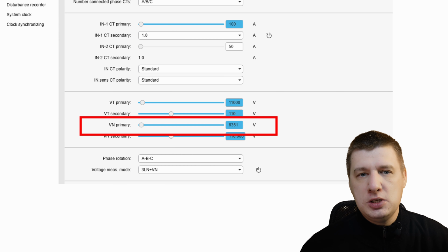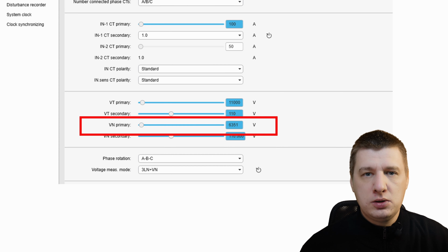When the relay measures the displacement through the broken delta VT, or calculates it from phase voltage, it uses the value as its anchor to determine if your neutral point has shifted too far during the fault. To set this up, we look at the scaling in the general menu. We'll see VN primary, and we have to match it to the VT primary neutral rating. If your measurement mode is three line-to-neutral, the relay will often default this to your phase-to-ground value automatically. Get this right, and your fault protection will be pinpoint accurate.